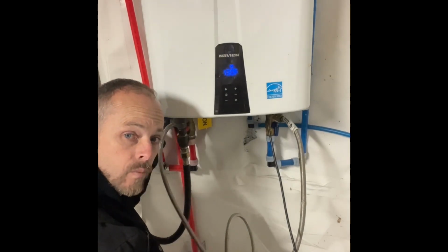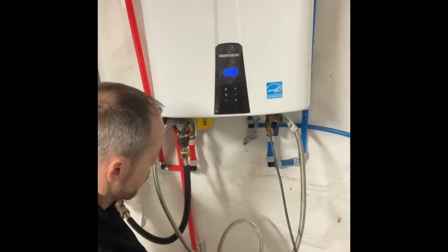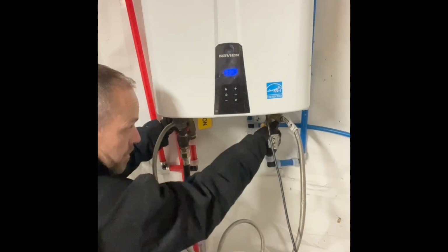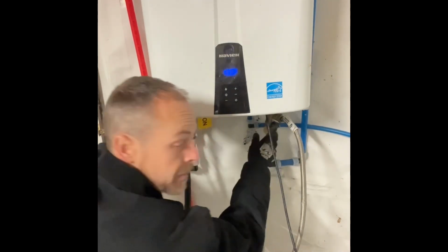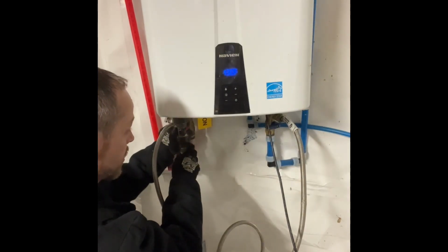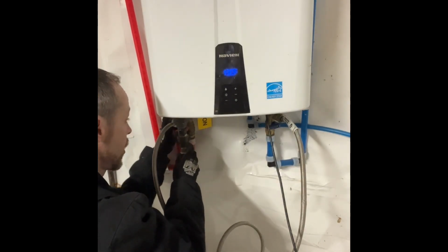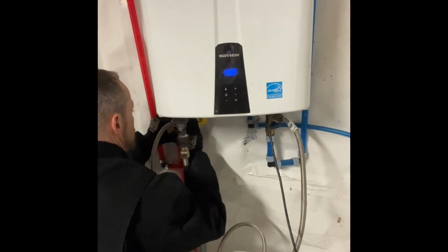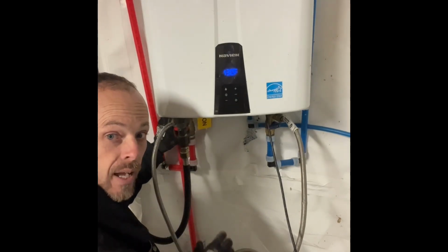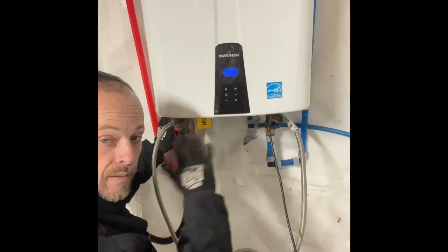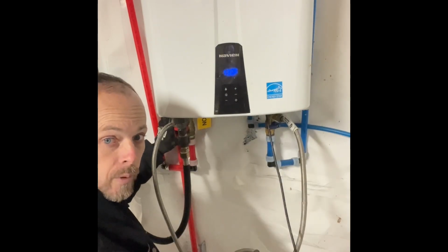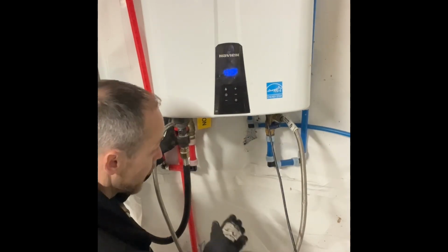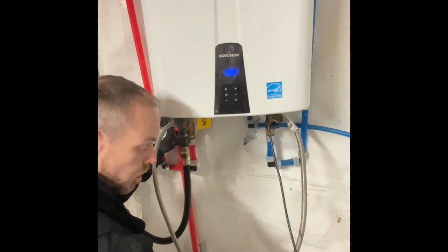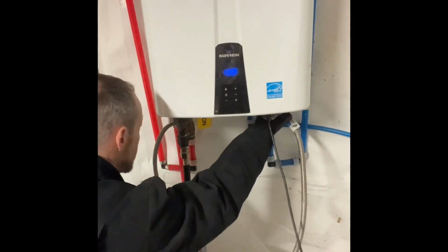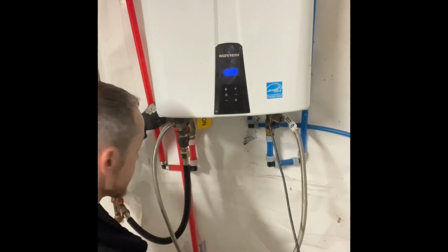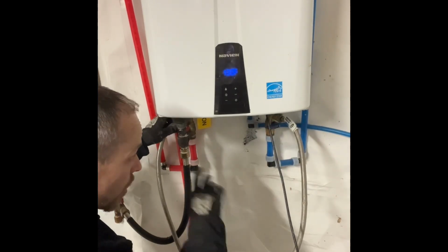Now that we have it full of water, we'll shut the water supply incoming to the tankless, and shut the water supply outgoing on the hot side that feeds the house. That way we don't have any flush solution contaminating the rest of the house or pushing back into the fresh water. Now that those are both closed and our hoses are in the bucket, we can proceed with opening the isolation valves on hot and cold.